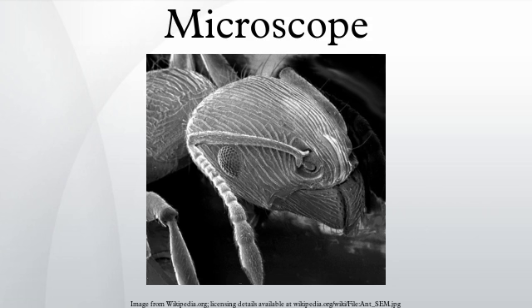In 1893, August Köhler developed a key technique for sample illumination, Köhler illumination, which is central to modern light microscopy. This method of sample illumination gives rise to extremely even lighting and overcomes many limitations of older techniques of sample illumination. Further developments in sample illumination came from Fritz Zernike in 1953 for inventing phase contrast, and Georges Nomarski in 1955 for his development of differential interference contrast illumination, both of which allow imaging of unstained, transparent samples.